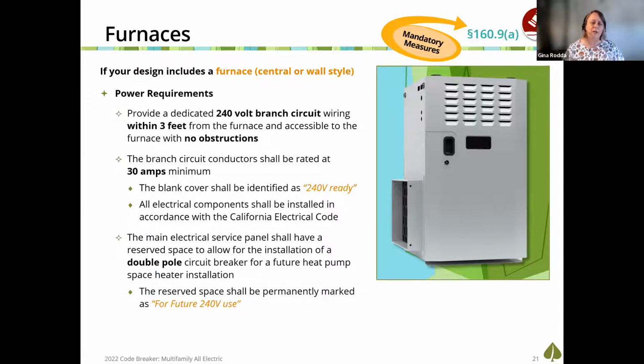If I put in that gas furnace, I will also have to make sure I design and install 240 volt branch circuit wiring within 3 feet of the furnace, and it's accessible. You can't block it off with cabinetry, etc. It has to be available, and that wiring has to be installed.